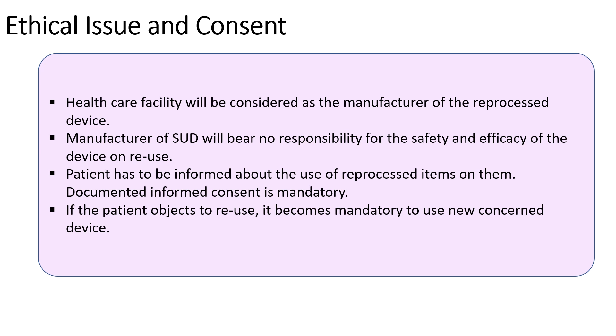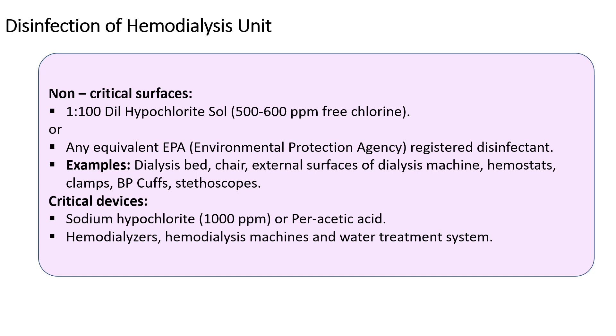For non-critical surfaces, use 1 to 100 dilute hypochlorite solution or any equivalent EPA-approved disinfectant, that is Environmental Protection Agency approved disinfectant. Examples are dialysis chair, external surfaces, and others. For critical devices, use sodium hypochlorite or peracetic acid, for hemodialysis machines and others.